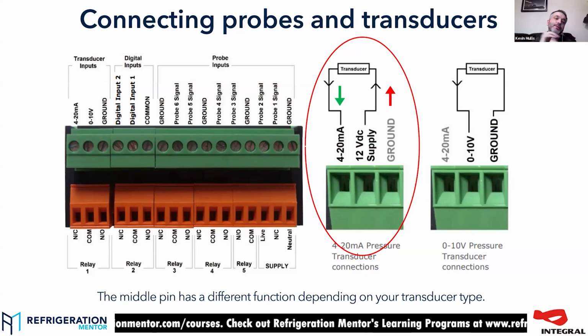So just to touch on the probes, again, as we said on our previous controller training, everyone likes the probes in their own order. So for RDM, probe 1 is your air on, your return air. Probe 2 is your air off, your discharge air. Probe 3 is your evaporator inlet, which in the absence of a transducer is your evaporating temperature for your superheat calculation. Probe 4 is your suction probe.